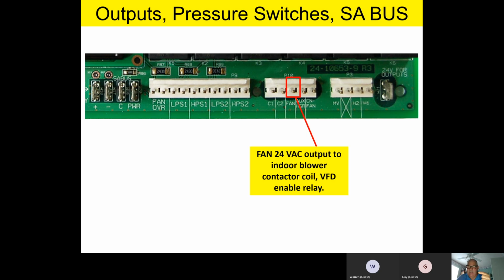frequency drive enable relay. So the way to think about this, on a thermostat, when I get a G call, if all permissions are met, in other words, if the board safeties are closed and all that stuff, and I get a G call from the thermostat, the board will interpret that as a command for fan. It'll then output 24 volts here to either bring a contactor on, to bring on a conventional fan motor, or it will put out 24 volts to a variable frequency drive enable relay to bring the fan on. So just think about this as basically the final output on a G call or a fan call.